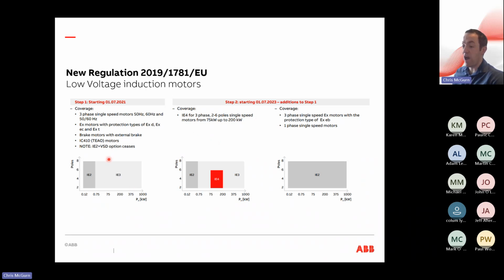Previously, before this, it was IE3, which covered 0.75 up to 1,000, and certain ones weren't considered traditionally, maybe 5 or 10 years ago. Ex motors for explosive environments, they weren't considered. They are considered now because of some of these new steps of legislation. Brake motors, again, originally were not considered. They are considered now, so that's something you have to keep an eye out for.